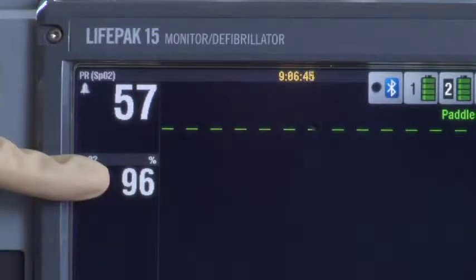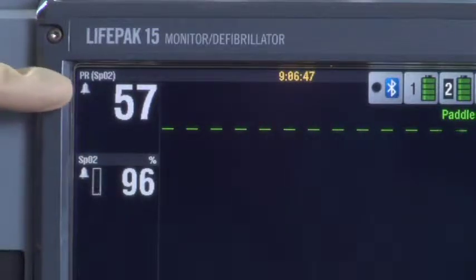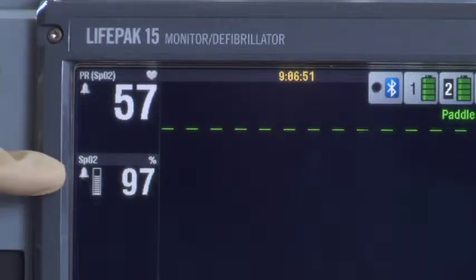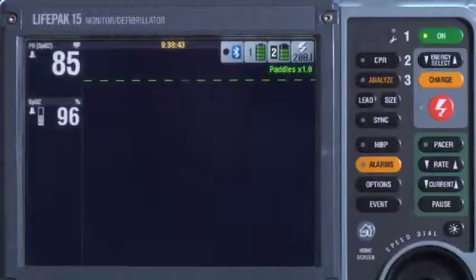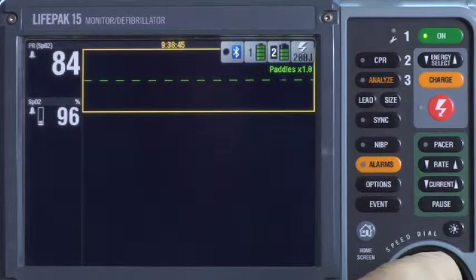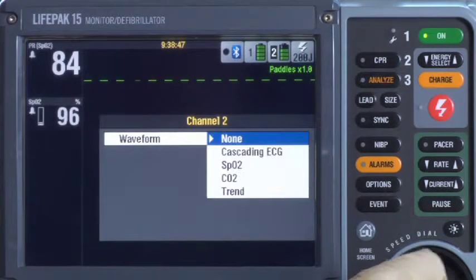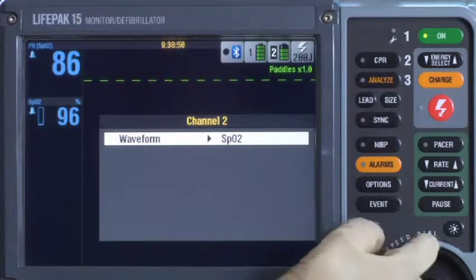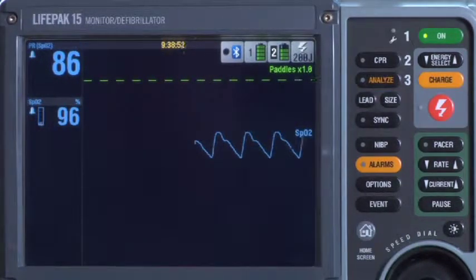If you use SpO2 alone, without ECG monitoring, the SpO2 pulse rate is shown here. The height of this bar indicates the quality of the signal. If you want, you can display the SpO2 plethysmograph, or pleth waveform, on the screen. Use the speed dial to outline channel 2 or 3. Click it and scroll through the channel menu to select SpO2. The waveform is automatically sized for optimum viewing.